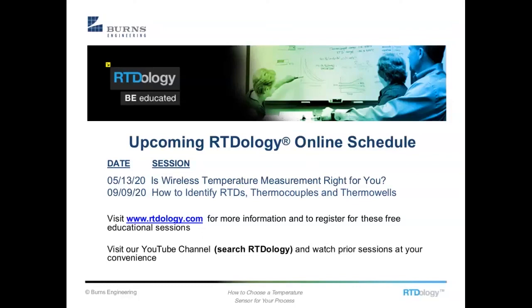I guess the only other thing I can add is that essentially a thermowell will heat up to the temperature of the process that it's in. Over time, there may be a time response issue where it's going to take longer for that thermowell to heat up and cool down than it would for just the sensor itself. But eventually, it will get to the same temperature. And if you have sufficient immersion, then you don't have to worry about what's happening on the outside of the process. As long as you're far enough into the process, the impact is so small that it's not going to be noticed. Hopefully that answers your question. If it doesn't, feel free to send us an email, and we'll try to get you what you're looking for.